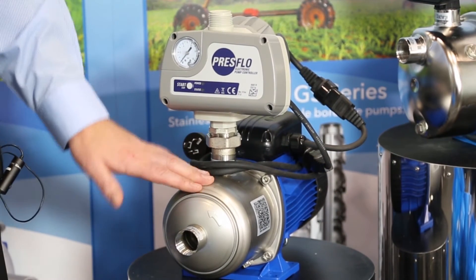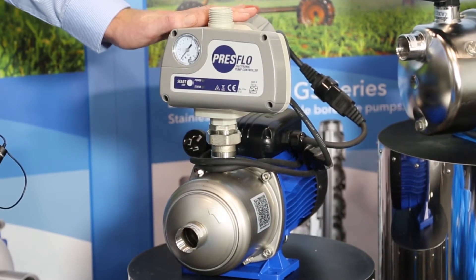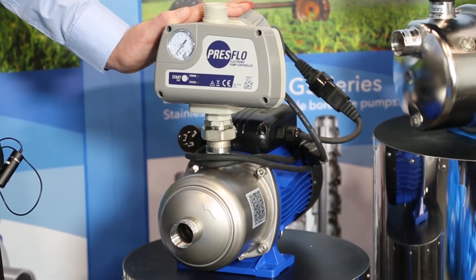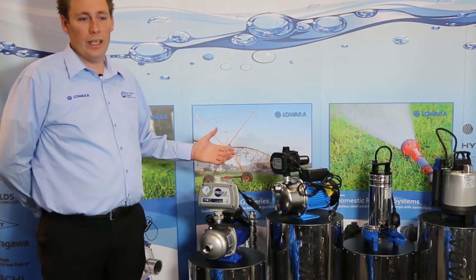These pumps are made in Italy. They're available with Noryl and stainless steel impellers, and a 304 stainless casing. The controller we use on it is Pres Flo. It has run dry protection, preset starting pressures, and also overload protection. Very high efficiency — we're generally a very small motor compared to our competitors.